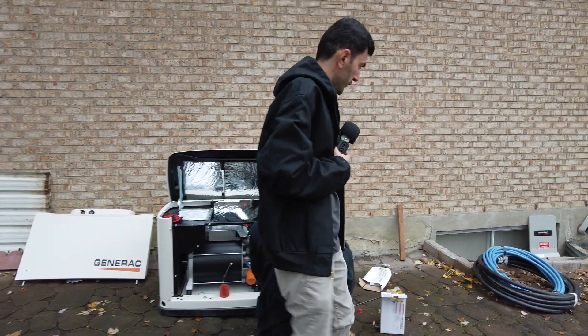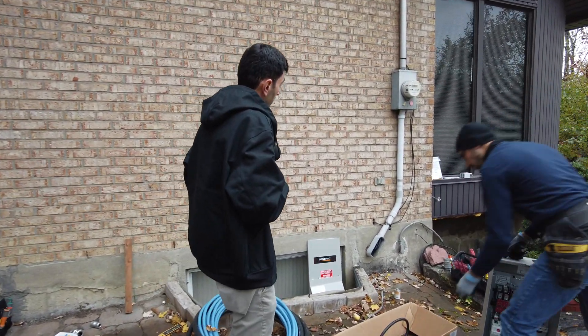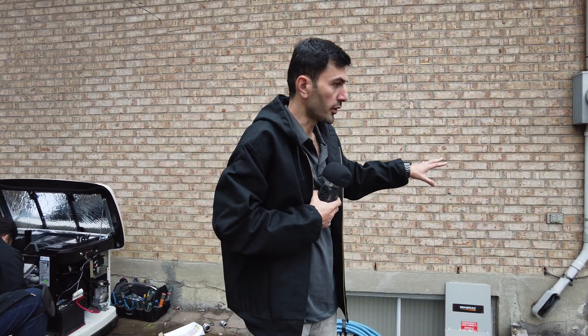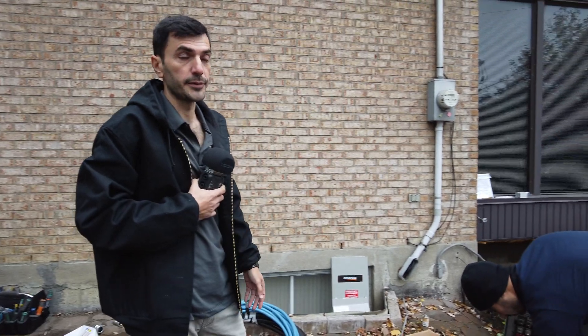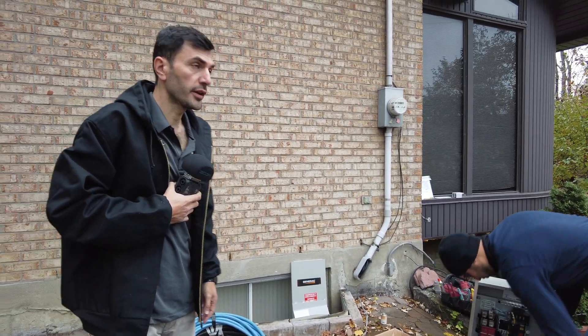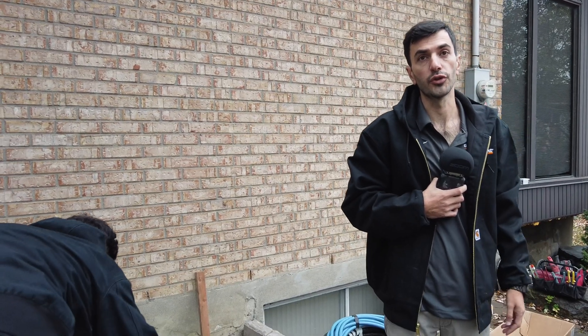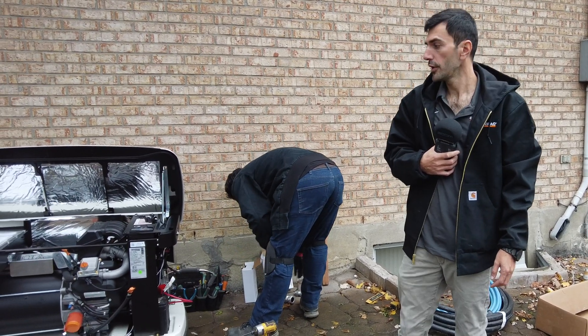My colleagues are working on the generator and the transfer switch. The transfer switch is going to be outside — when there is a power failure it is going to kick on and give power to the whole house. Everything in the house will be functional, but the modules on the hot water tank and the furnace will postpone those two items to protect the generator from being overloaded.